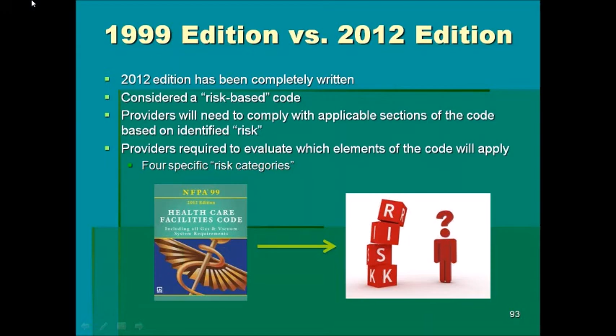Under the newer editions of NFPA 99, and specifically the 2012 edition, a risk assessment is required whenever changes occur within your facility. It's probably a good time to mention this. If you're that administrator that's on the call right now, and you've always struggled with what you can buy that maintenance director or facilities management vice president the next holiday season, think about buying them the Life Safety Code Handbook or the NFPA 99 Handbook, because not only does it explain the code in its entirety, it is filled with other resourceful information that further explains the applicability and the integration of the code within your facility.